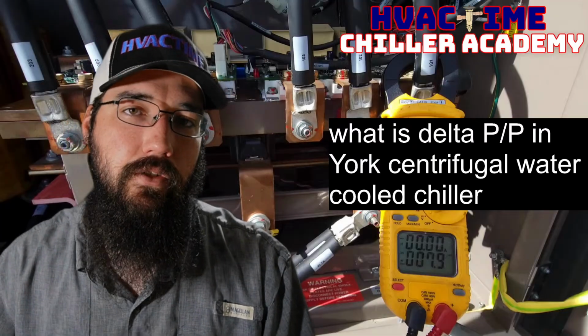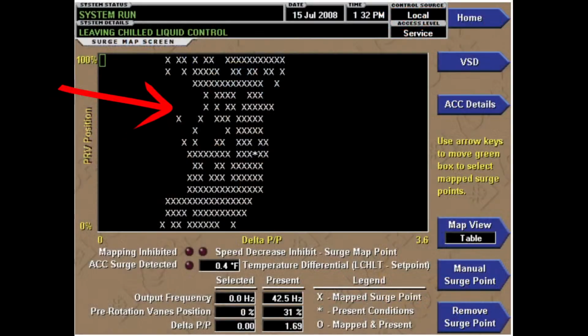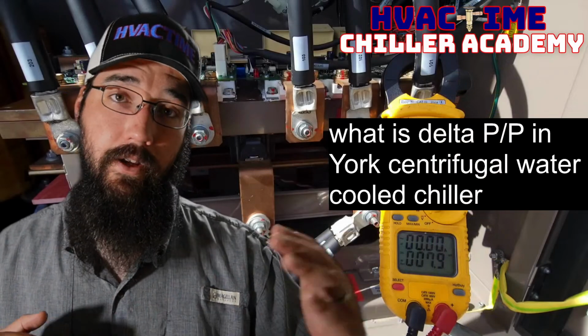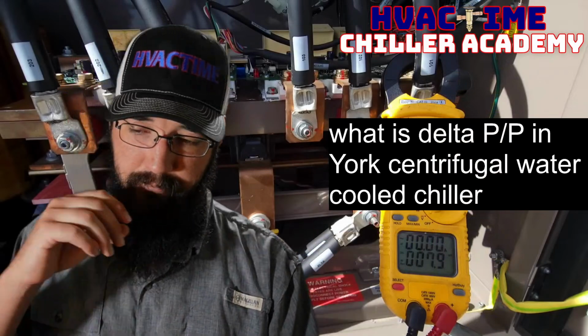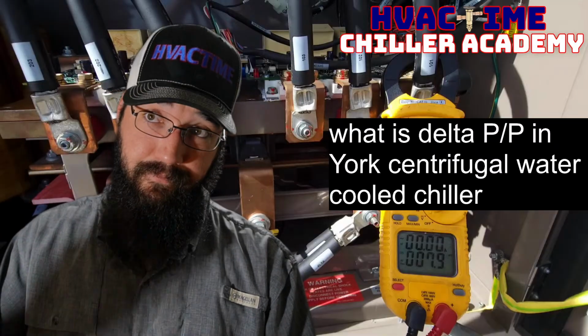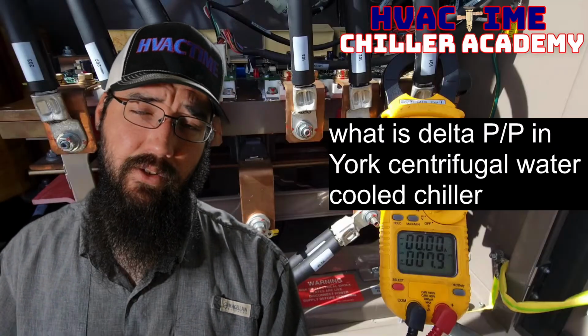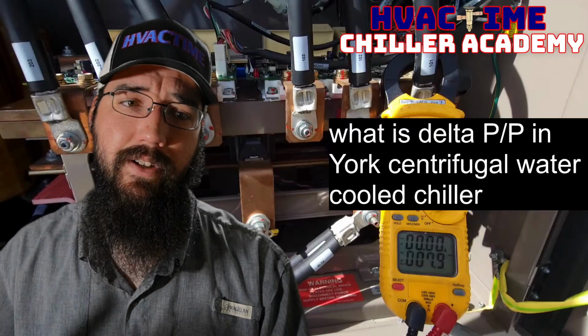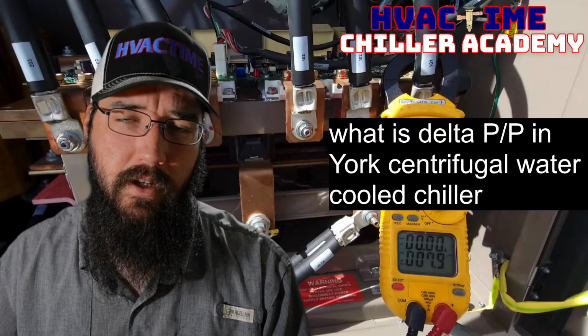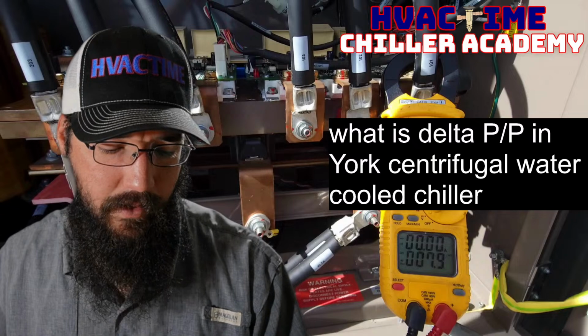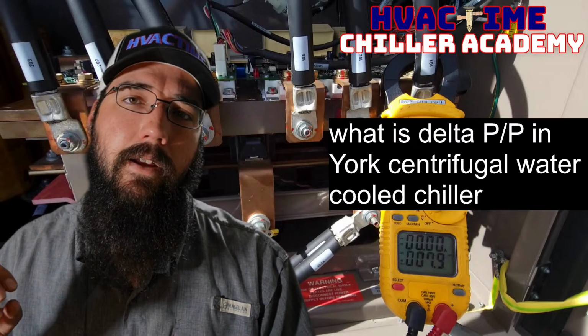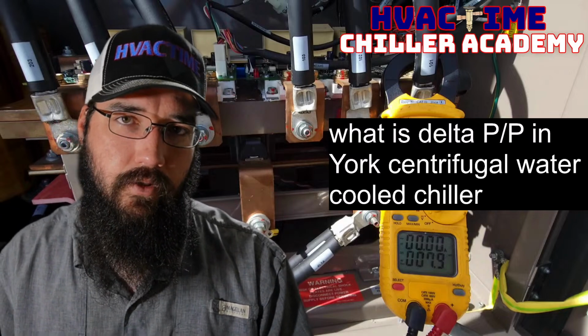That increased surging is going to start creating a lot of mapped points here. Those extra points on the map now become points that you're trying to avoid, so that the machine is intentionally trying not to continue surging, so that it protects itself and protects the bearings as much as possible. That's the whole thing it's trying to accomplish. And this is something that a lot of other chillers don't have.